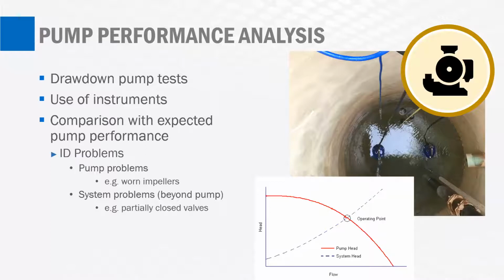It's also important to recognize that pressure gauges are a really important part of the pump performance analysis. There are many pump stations out there that don't have pressure gauges. What would typically be recommended prior to the pump station audit is that pressure gauges be installed on the force mains, typically in the valve vaults. The reason those pressure gauges are so important is that they help us determine the true pressure that the pumps are operating against. That true pressure is, in essence, the total dynamic head in the system.